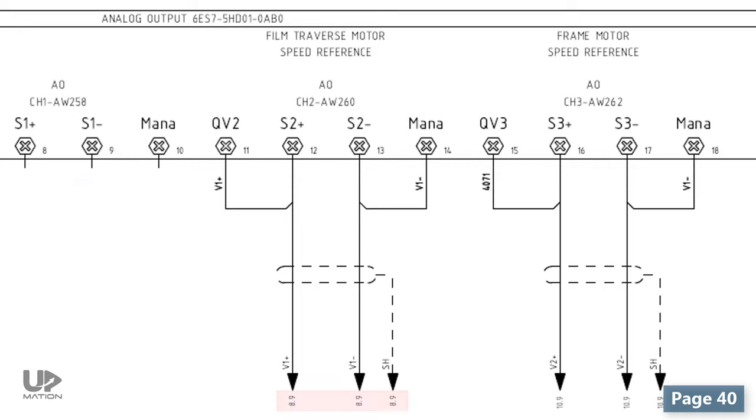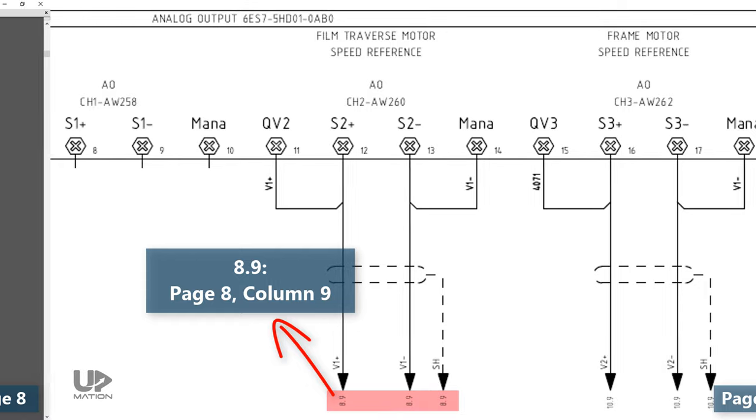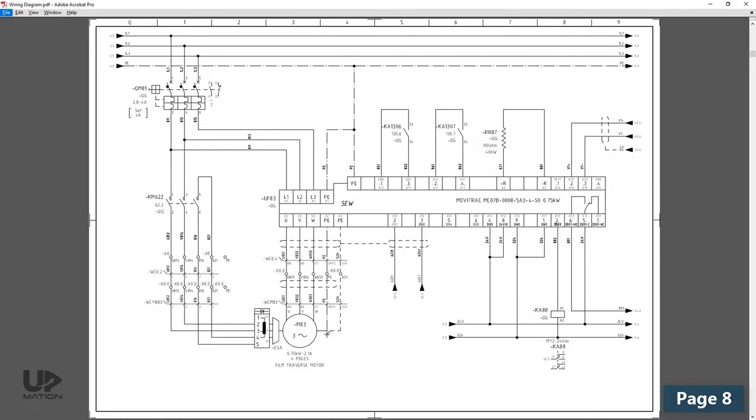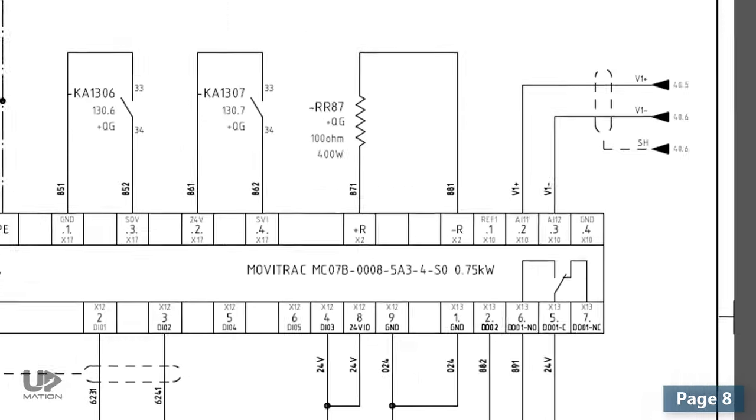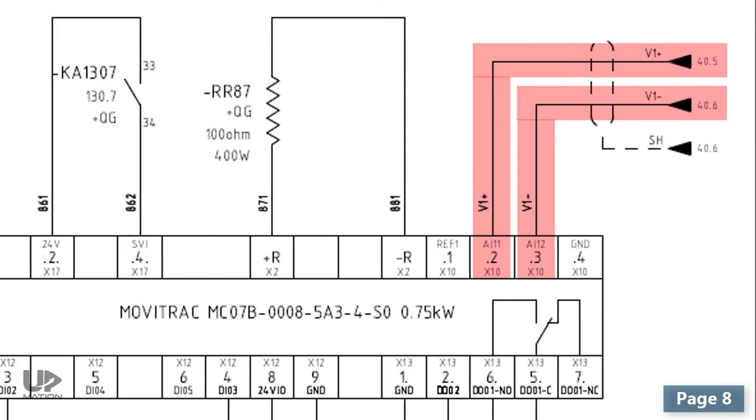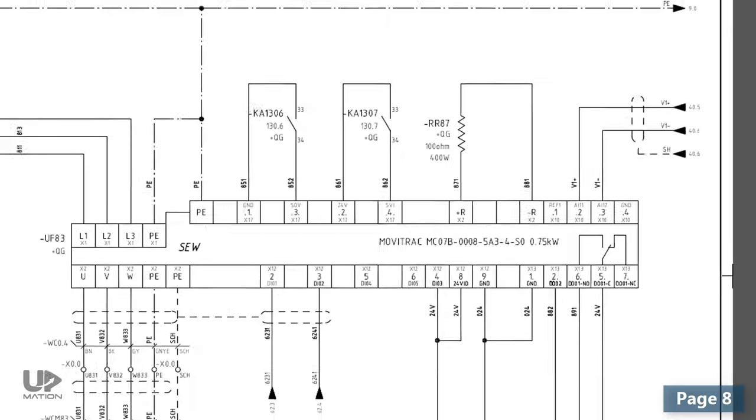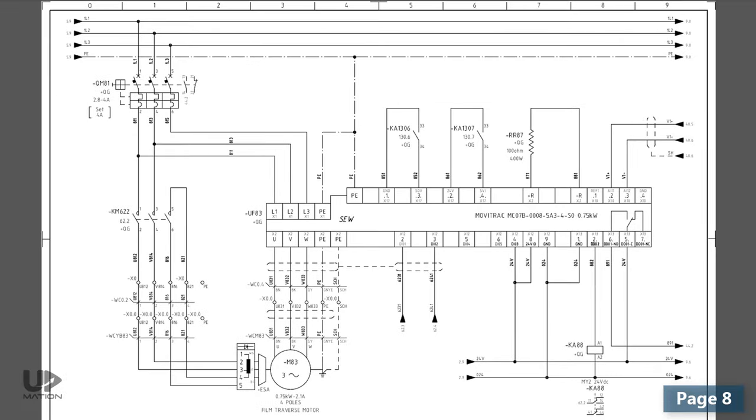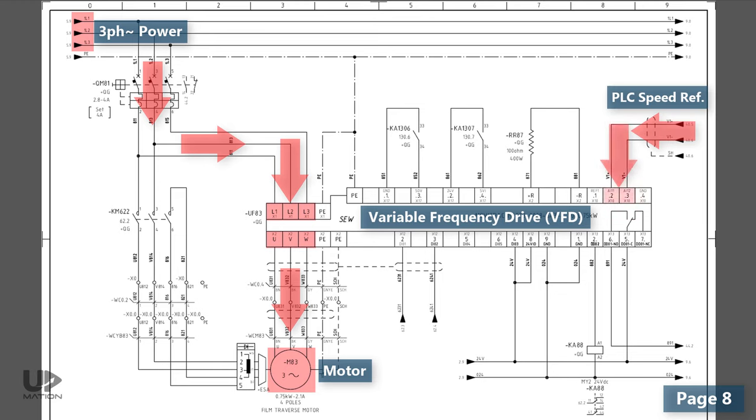If I turn to page 8, column 9, we see that our speed reference output is connected to the terminals of an SEW VFD. On this page, we generally see that the AC three-phase power is connected to the inputs of the VFD. And the VFD is adjusting the power flowing toward the electric motor according to the speed reference it's receiving from the PLC analog output card.